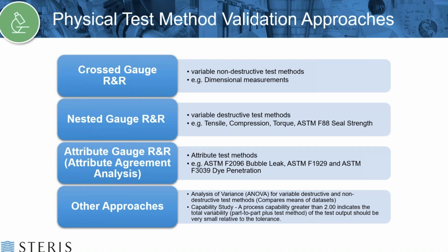There are a number of ways to approach a test method validation. By far, the most common we would see is the gauge R&R statistical approach. It's a technique that's widely used to analyze test data. The purpose of it is to determine the repeatability and the reproducibility of a study. Repeatability is the variation between successive measurements of the same part or trait by the same person using the same equipment. In other words, one operator's ability to get the same result on the same part every time.